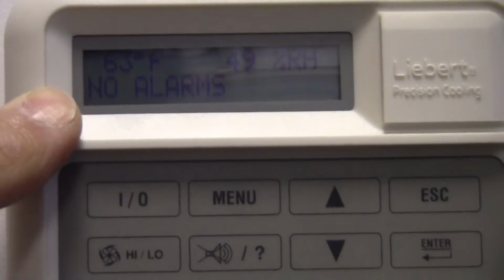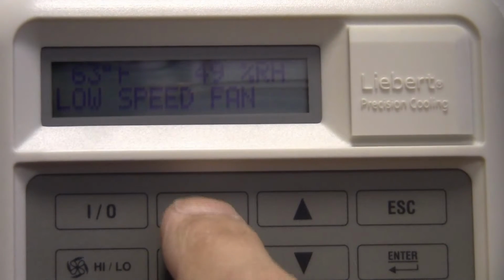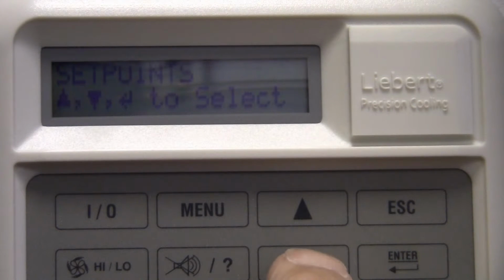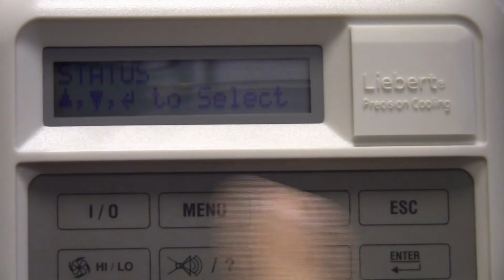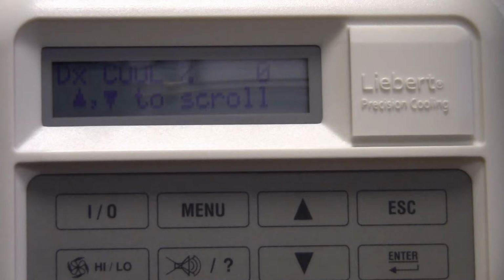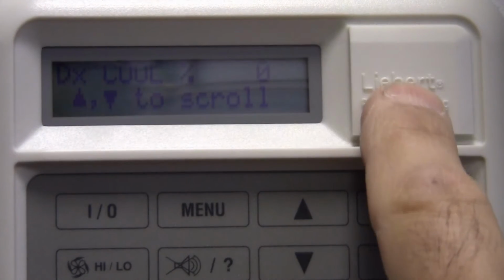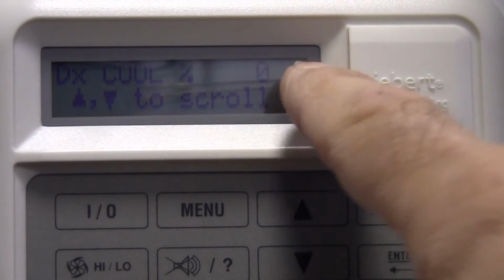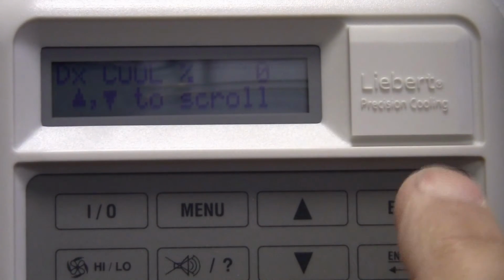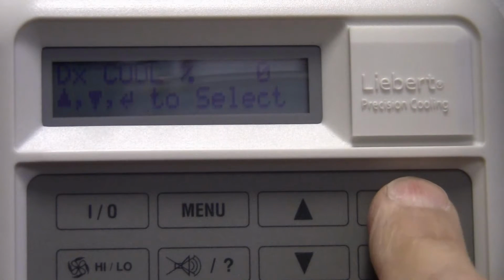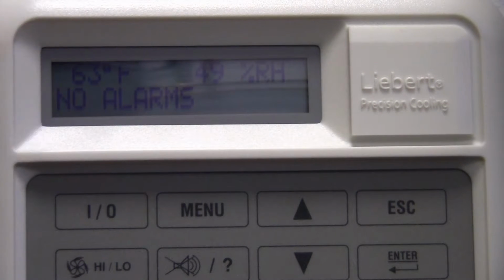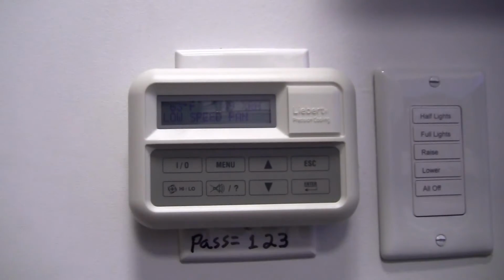Now, first thing I want to do is hit the menu button, scroll down to where it says status, and hit enter. It's going to tell me that the thermostat wants 0% cooling. There's no cooling signal, as there should not be, because it is 63 degrees Fahrenheit. So the thermostat signal is telling the unit you should not have a compressor on. I don't know if you can hear it in the camera, but I can tell you the compressor is running right now.